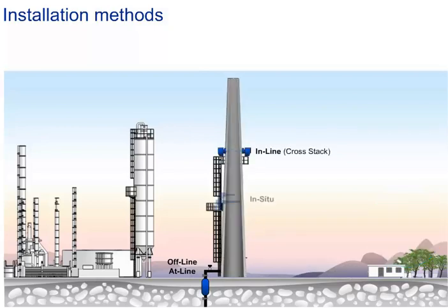To measure directly in the stack, extraction probes and analyzers are mounted together at the measuring point. This is called in-line or in-situ measurement. Finally, there is the extractive measurement, where the sample gas is fed continuously from the process line to an analysis system. It can be installed near to the measurement point or at a short distance, and the gas can be conditioned before it enters the gas analyzers.